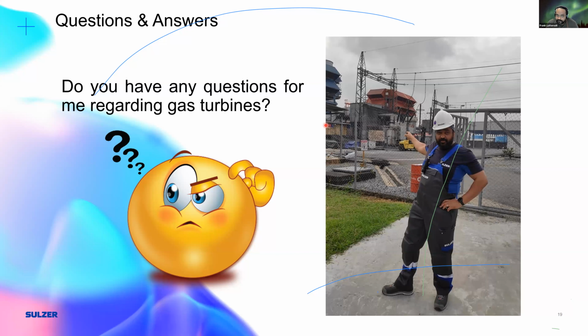If you really do have a problem and you perform the live overspeed test, the worst case is you could damage the equipment. So if it's not required by law or by the insurance company to demonstrate it, you'd always fall back to a simulation where you activate the individual channels, trip the unit, and demonstrate that the protection of the system is guaranteed in the case of an overspeed scenario.